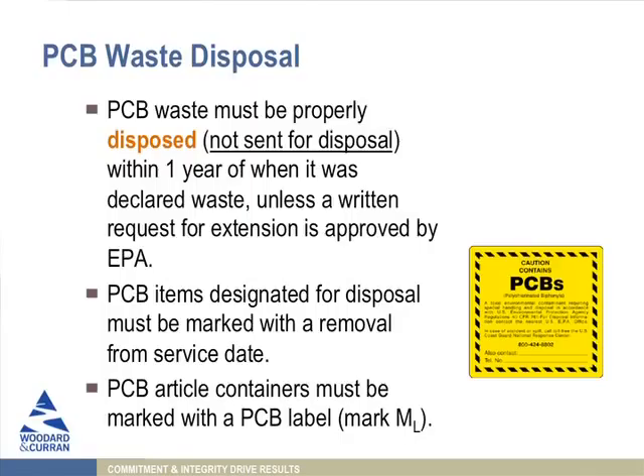The paperwork, we'll get to that, because there's a concept similar to what the hazardous waste regulations call for. To show you've disposed of it within a year, you have to mark it with a removal from service date, which is when it becomes a waste. So when you take a ballast out of a light fixture, you write the date.